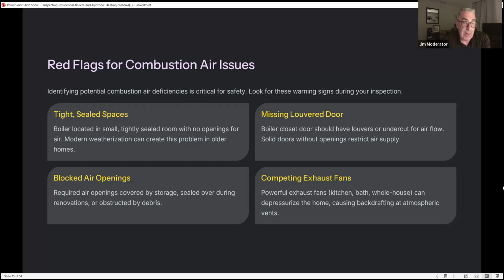Blocked air openings: required air openings covered by storage, sealed over during renovations, or obstructed by debris. Missing louvered door: boiler closet doors should have louvers or an undercut for airflow. Solid doors without openings restrict air supply. Competing exhaust fans: powerful exhaust fans, like kitchen, bath, or whole house fans, can depressurize the home, causing backdrafting at atmospheric vents.